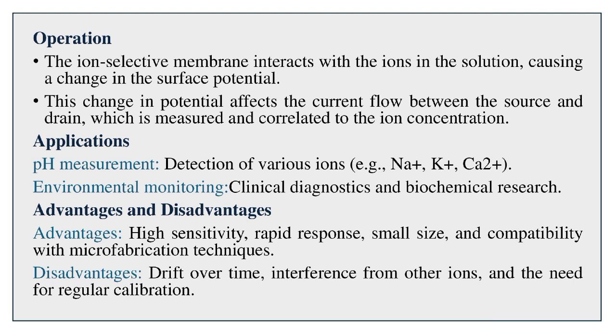ISFET Advantages and Disadvantages. Advantages: high sensitivity, rapid response, small size, and compatibility with microfabrication techniques. Disadvantages: drift over time, interference from other ions, and the need for regular calibration.